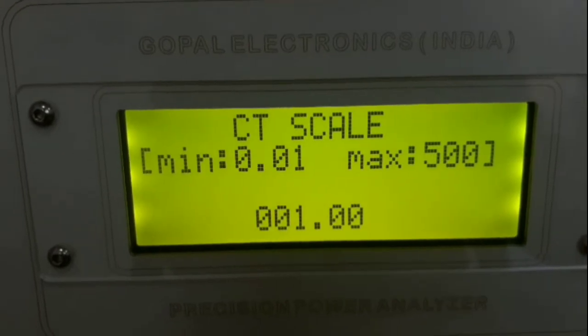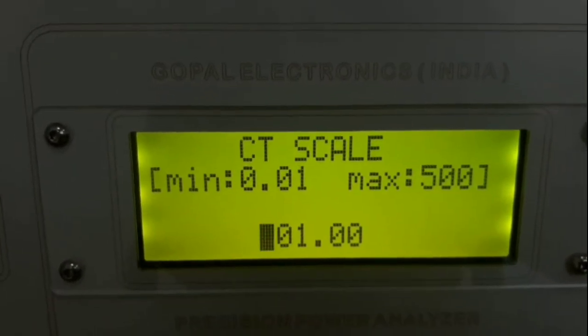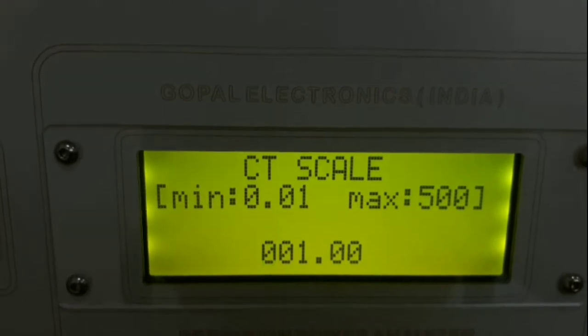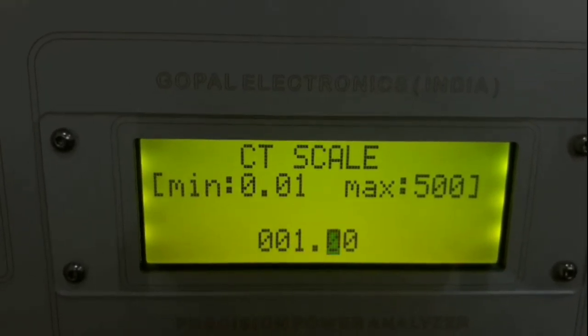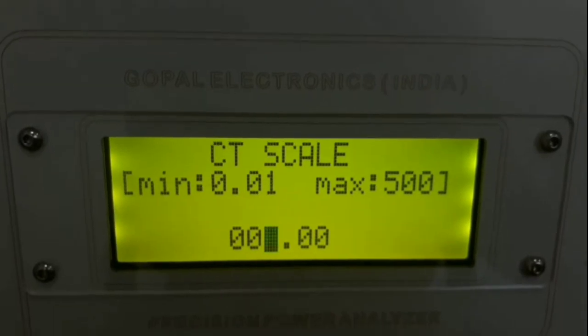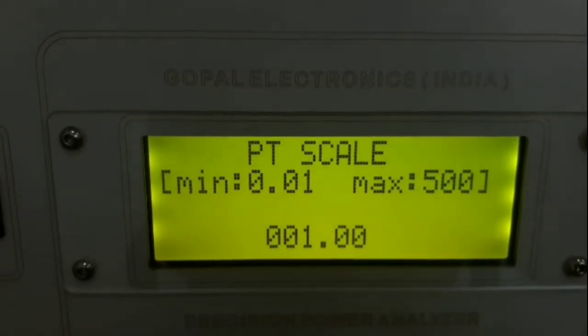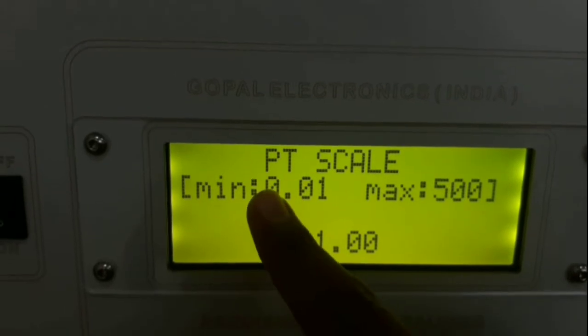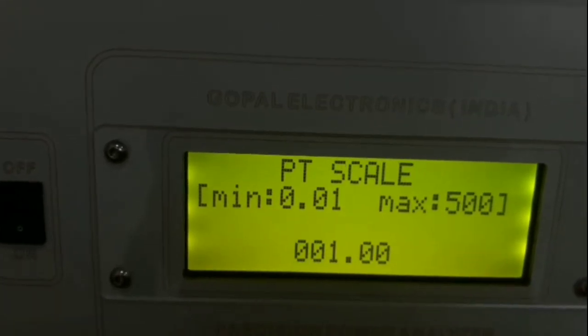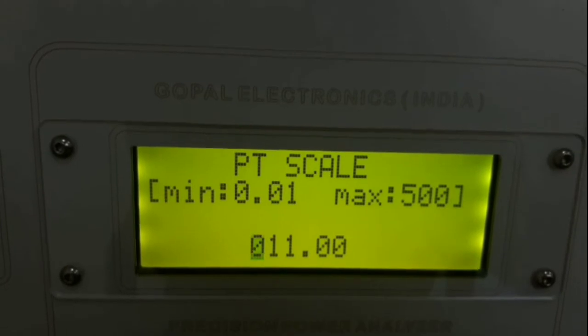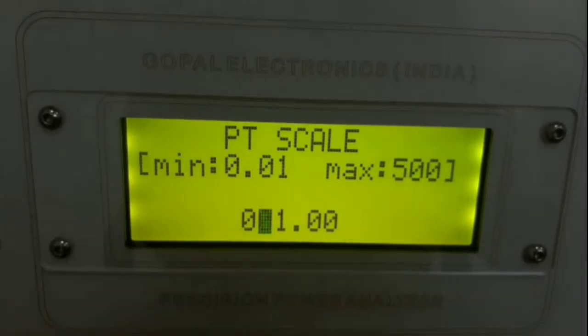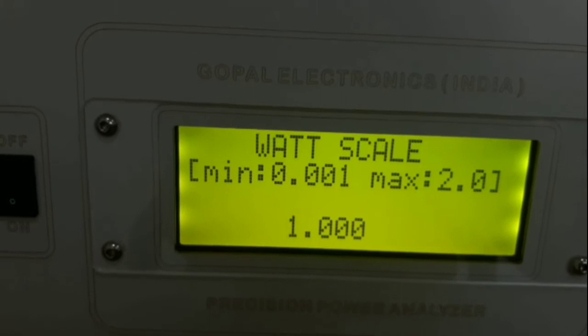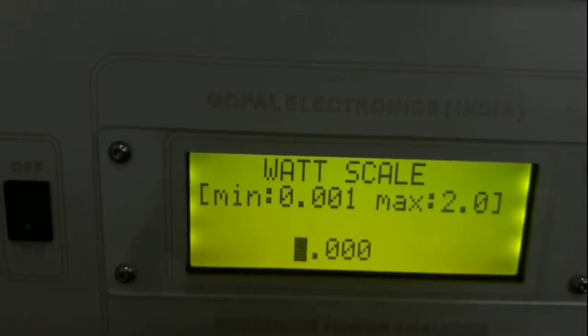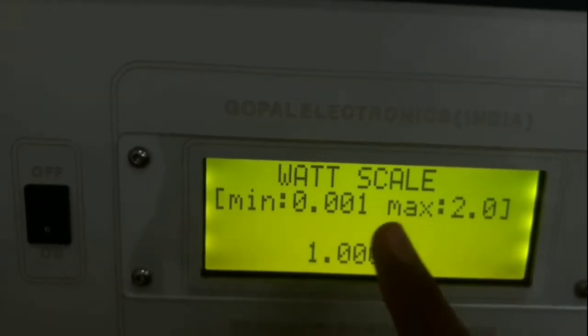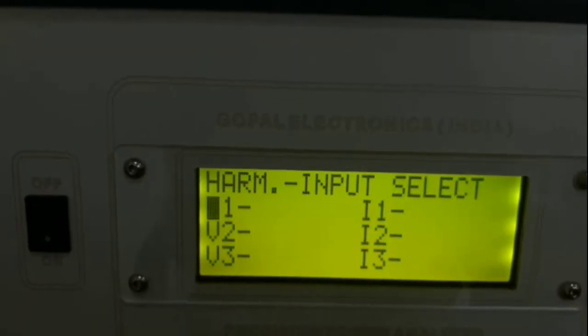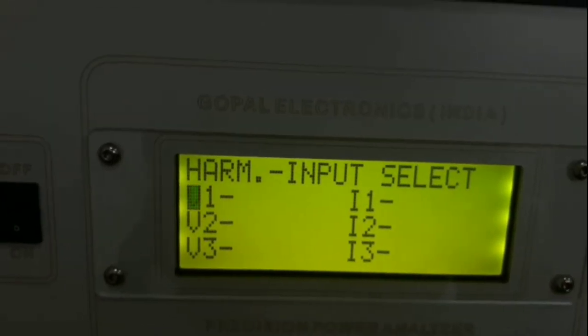Then you will come to CT scale. By pressing the up down key, you can select the value, and by pressing the right key you can go right and left. Press enter. Now you will be in PT scale. You can see that the minimum and maximum ranges are mentioned above. By pressing the right key or left key and up key and down key, you can select the range and enter the value. Same for watt scale, the minimum and maximum range is given and you can enter the value. Press enter. This is harmonic input selection. Press exit.